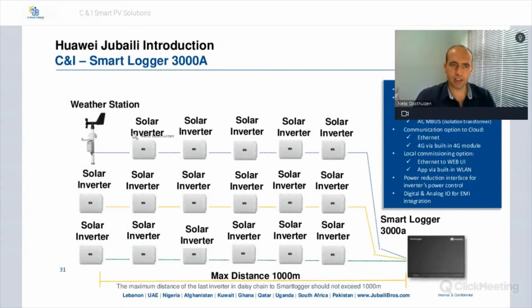Please note that if you do a daisy chain between inverters and you have a weather station, it should be the last in the daisy chain and not the first one or even a random number in between. So if you do make use of a weather station, make sure that it's the last one in the daisy chain. As I've mentioned, the maximum connected devices is 80. Communication interface is RS485. Also, you can use AC M-Bus. Communication options to the cloud are either Ethernet or 4G via the built-in 4G module.